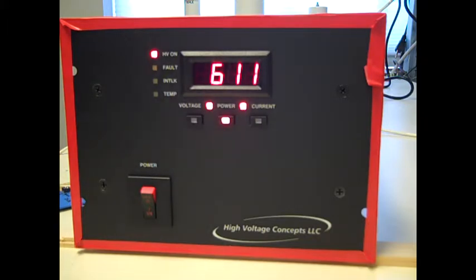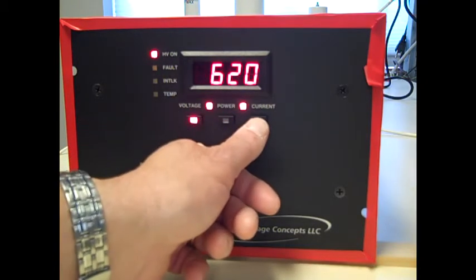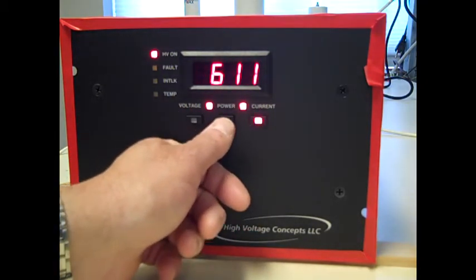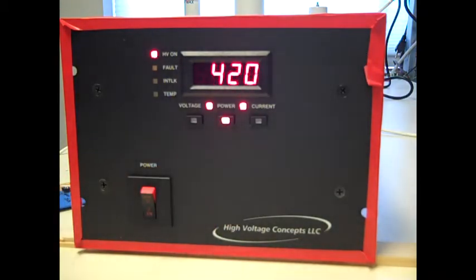Now I can adjust down this voltage for the reference for the power, and we can see the power being reduced. And of course with that we can see the voltage being reduced because we're in power mode. And we'll turn the power back up again, to around 600 or so. And now we're going to put a little bit heavier load on and go into current mode so we can show you what that looks like.